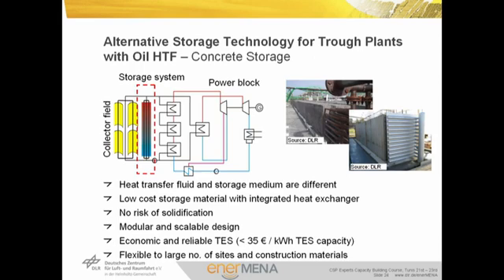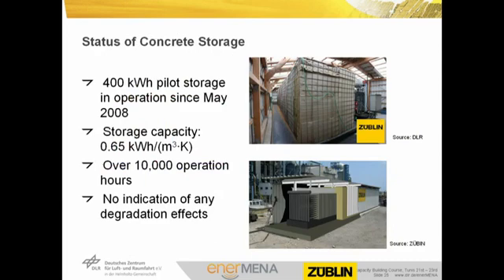Another advantage is the option to use construction materials available at the construction site. Thermal energy storage using concrete as storage material has been demonstrated at pilot scale. A 400 kilowatt hour storage unit has been in operation since May 2008. The storage capacity is in the range of 0.65 kilowatt hours per cubic meter per Kelvin. The pilot scale unit has been operated for more than 10,000 hours, and so far no indication of any degradation effects has been identified.